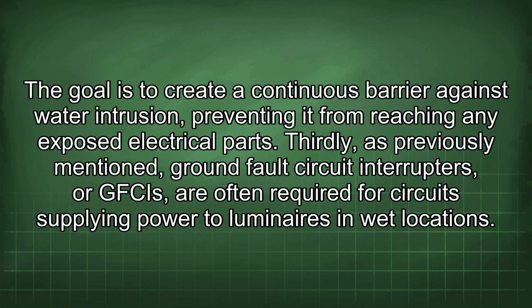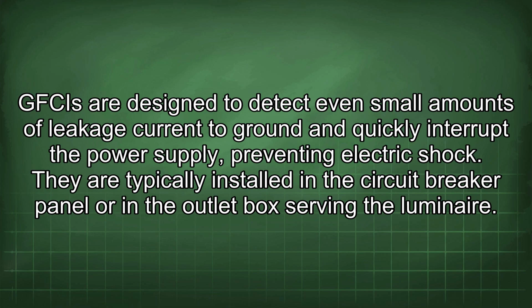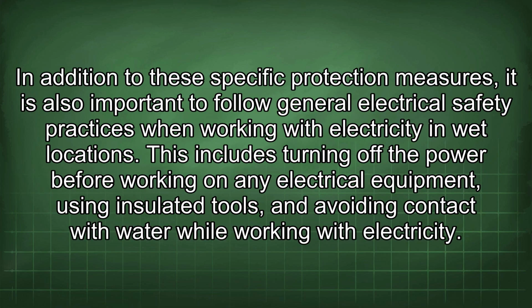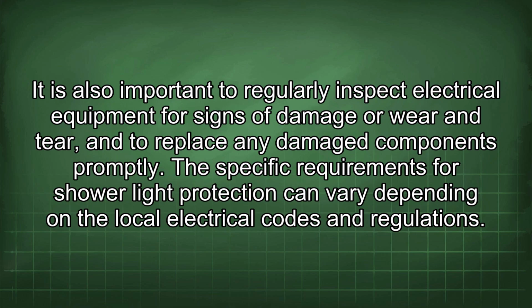Thirdly, as previously mentioned, ground fault circuit interrupters, or GFCIs, are often required for circuits supplying power to luminaires in wet locations. GFCIs are designed to detect even small amounts of leakage current to ground and quickly interrupt the power supply, preventing electric shock. They are typically installed in the circuit breaker panel or in the outlet box serving the luminaire. In addition to these specific protection measures, it is also important to follow general electrical safety practices when working with electricity in wet locations. This includes turning off the power before working on any electrical equipment, using insulated tools, and avoiding contact with water while working with electricity. It is also important to regularly inspect electrical equipment for signs of damage or wear and tear, and to replace any damaged components promptly.